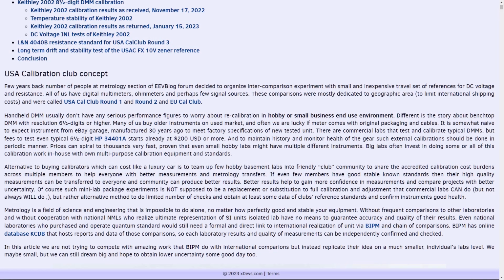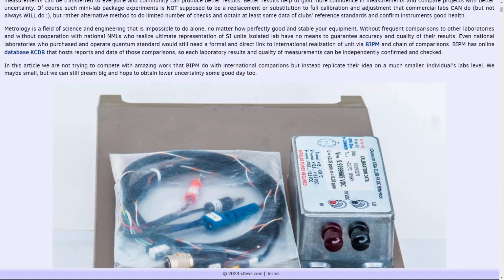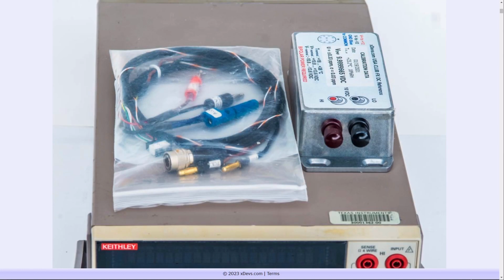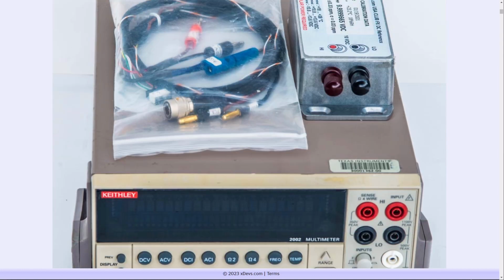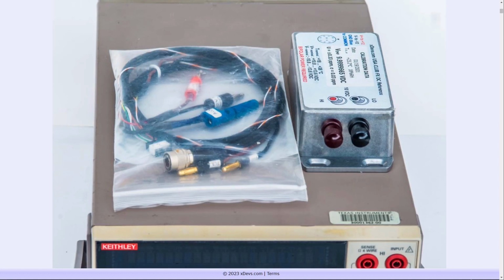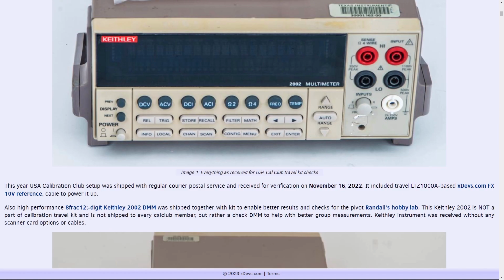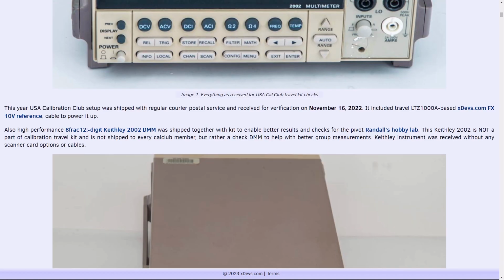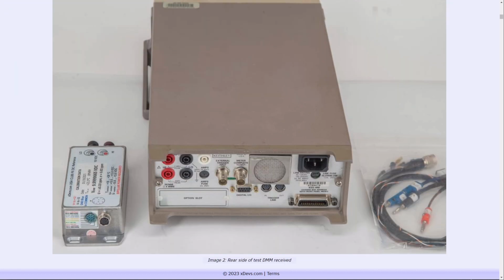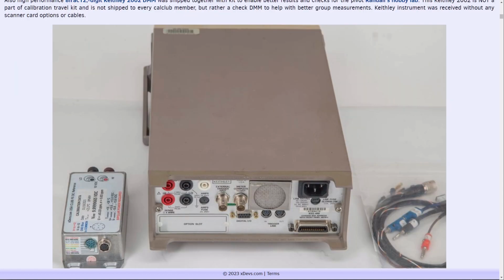In the beginning of the article, I give an introduction to this CalClub concept and show the calibration kit I received. So here is the Keithley 2002 with the DC reference called XDevs FX. It has the cable that comes with the reference, and the meter didn't come with any other cables. This instrument was originally bought used by Randall, and it was spot checked and calibrated at a few ranges, but we will see how it goes for everything else.